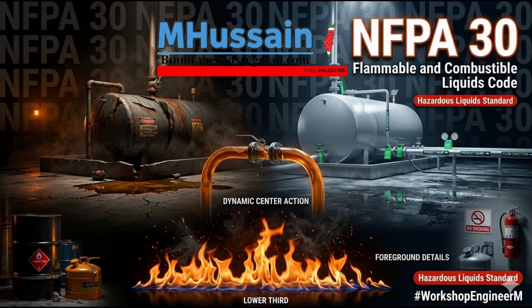Wow. And conversely, if a small ignition happens inside the cabinet, standard ventilation provides a continuous draft of fresh atmospheric oxygen, letting the fire rapidly consume everything inside. But if it's sealed? If it's sealed and unventilated, you restrict the oxygen. Any internal fire will quickly burn up the limited oxygen in the box and literally choke itself out. The NFPA prefers a concentrated, contained box of vapors over a ventilated box that breaches the firewall. That's the engineering philosophy in a nutshell.